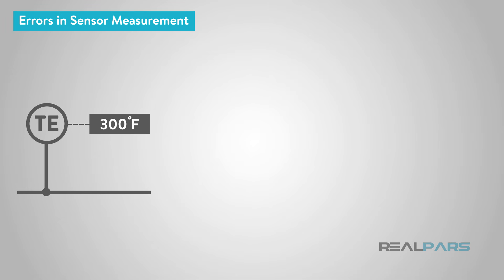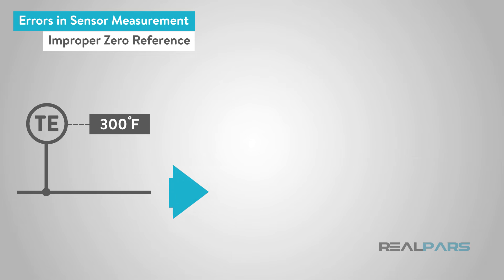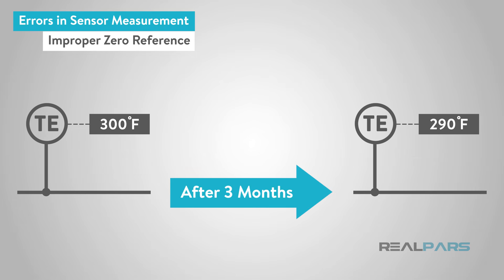First, the instrument may not have a proper zero reference. Modern sensors and transmitters are electronic devices, and the reference voltage or signal may drift over time due to temperature, pressure, or change in ambient conditions.